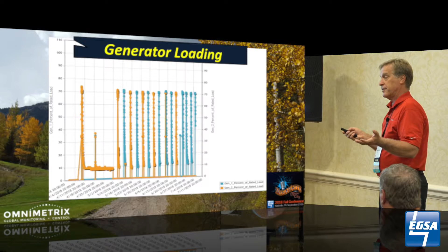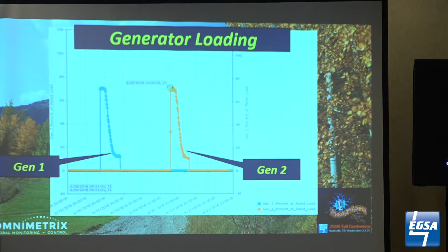So this is a week or two of data zoomed in. You can see this is an alternating design where one gen runs and then the next, and it flips back and forth. If we look at the peak loads on those two machines, sure enough, they're running right around 70% of rated load - a great number. You don't have to worry about the wet stacking situation. Of course this is propane, but it's an appropriately sized machine - there's no instance of it being over demanded.